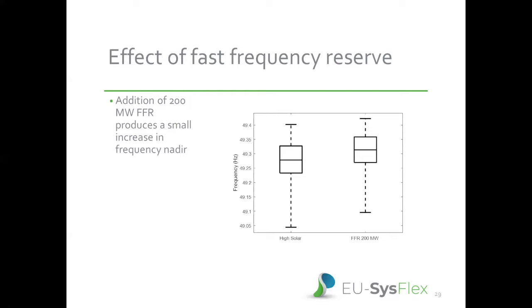In the picture, you can see two cases. These are both for the high solar scenario. We can see that with fast frequency reserve, the minimum frequency nadir increases about 50 millihertz if it's on the level of 200 megawatts. So this is also one way to fight against the low frequency nadir.